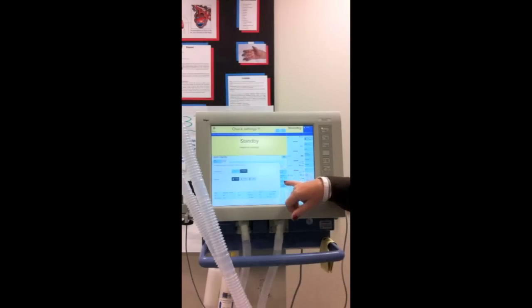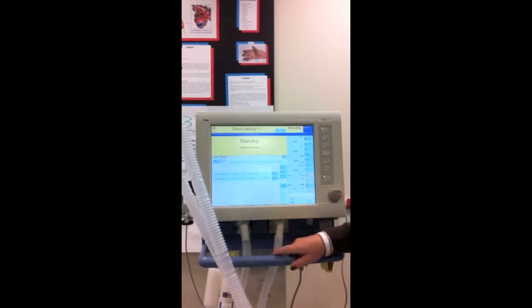So they have the check button. We also have oxygen, humidifier, tube, and mask, but we're going to go to the check button. And when you go to the check button, you'll see device check and airtight check. And you'll also see when they were done last. So you see this was last done yesterday. The last airtight check, which checks for leakage.